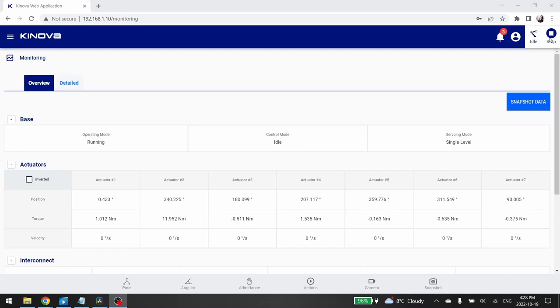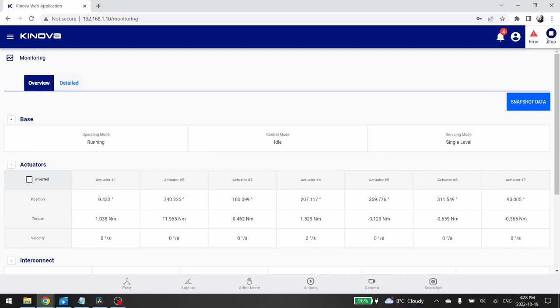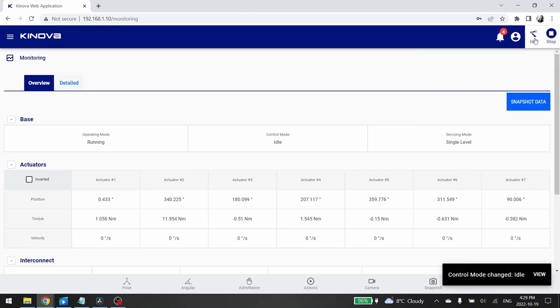Finally, you'll have the Stop button. It corresponds to a Software Emergency Stop. It will stop your robot and put it in fault. If you want to quit the fault state, you need to be sure that your environment is safe and then you need to go to the Robot State icon. Here, you will see that an error was raised. To clear it, click on the Clear All button. Then, few seconds later, the robot will be back to a normal state.